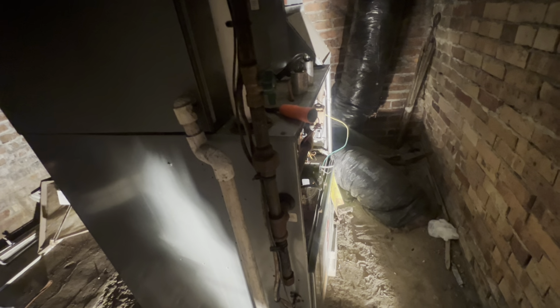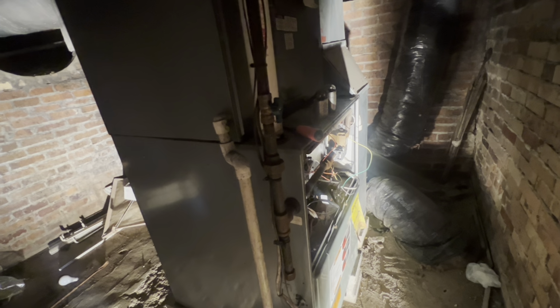All right, it's looking good. Wait for the blower. Good. All right, I just heard our blower come on. Our blower came on after a delay just like it was supposed to. We have flames. We are moving. Before I leave and walk away, I'm going to take a temperature split real fast to make sure the unit's working pretty good. Might take an amp draw or two on the unit itself, and we'll go from there.